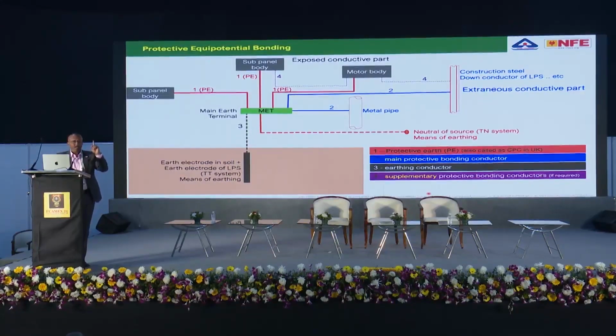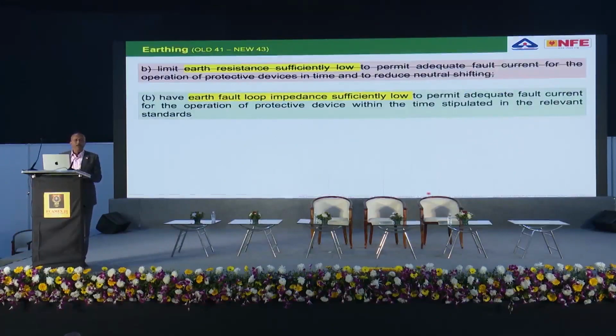The first safety measure, protection against shock, is this one. That means in any building, it can be residential or industrial or multi-storied, whatever, every building has to be divided into several locations, and depending upon the size of the building, each of the locations shall have this kind of equipotential bonding. This is what is written in the regulation. As I said, in 1937 this was also there, but the reading was different. This time the regulation made it crystal clear. So this is one of the changes. Like this, I can tell you maybe 100 changes came in these two documents. One of them, the second one, is fault loop impedance.